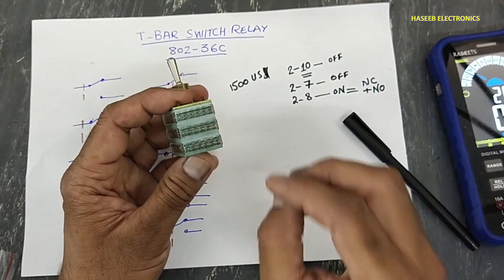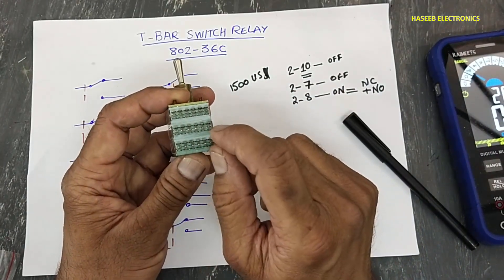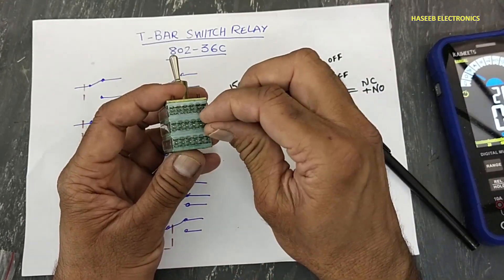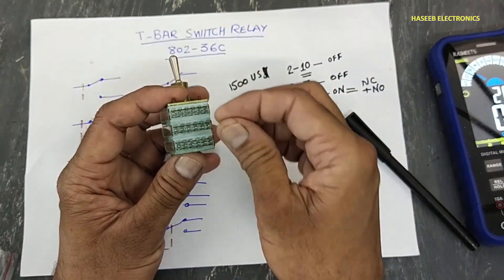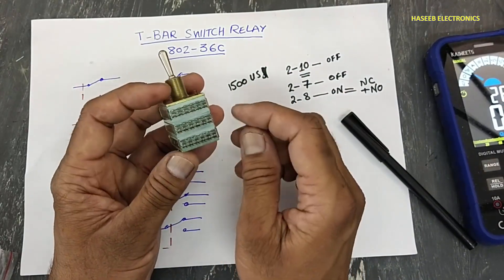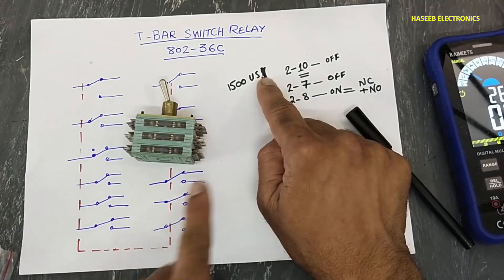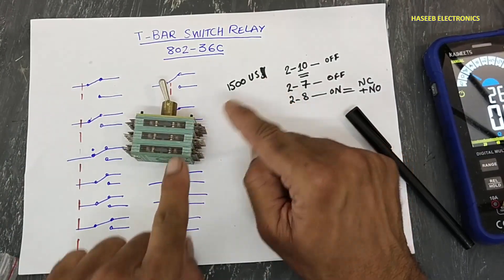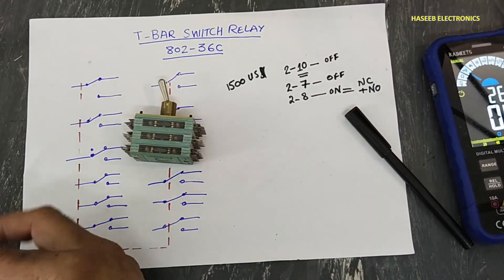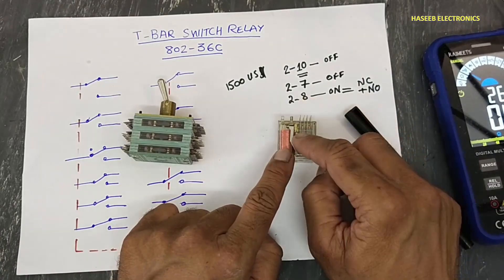The third solution: in the wiring we can find some spare locations that are free and have no wiring. We can remove the wires from the bad contacts and shift those wires to free switch locations. The fourth solution, if we don't have a new one, don't have a contact set, and don't have spare locations, we can use a multi-terminal relay.